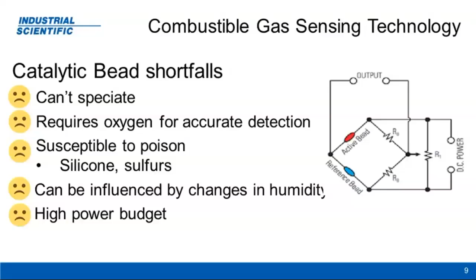How do we overcome those shortcomings? You'd think there's got to be a better mousetrap, since this technology's been around forever, and a lot of people think there is: infrared, non-dispersive infrared, or what today we call ULPIR, ultra low power infrared. Many see this as the cure-all for combustible gas sensing, and there are some good reasons why—there's no O2 requirement, so you can detect combustible gases in a completely inert atmosphere.